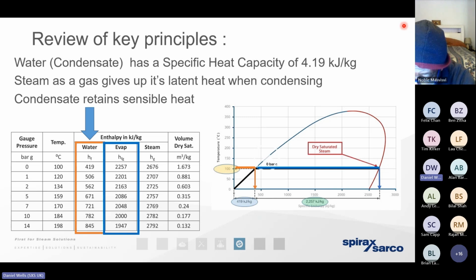journey in September. The steam tables and the values expressed in the steam tables, they're only applicable if we've got 100% dry saturated steam. If we've got steam that sits on that dry saturated steam line. If for any reason we've got wet steam, then not only are we going to get those mechanical issues, that erosion, corrosion, and water hammer, we're going to have those inefficiencies. Well, tonight's presentation is about decarbonizing steam. So I'm going to ignore the mechanical issues caused by a poor quality of steam. I'm going to focus on the inefficiencies instead.